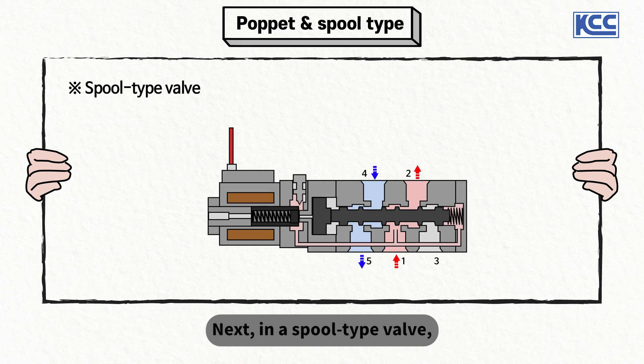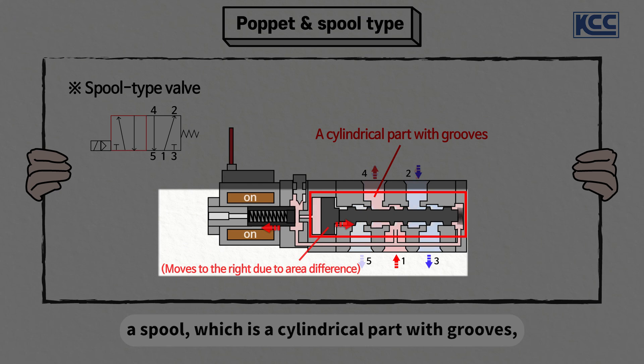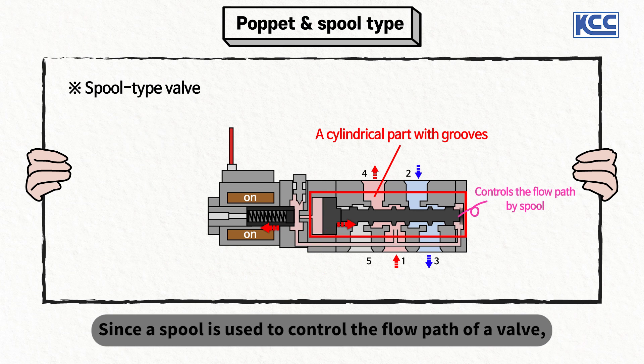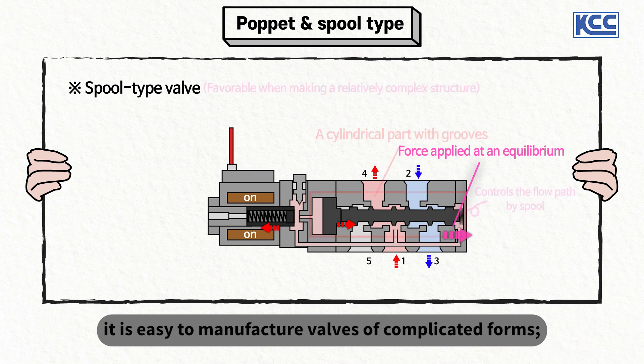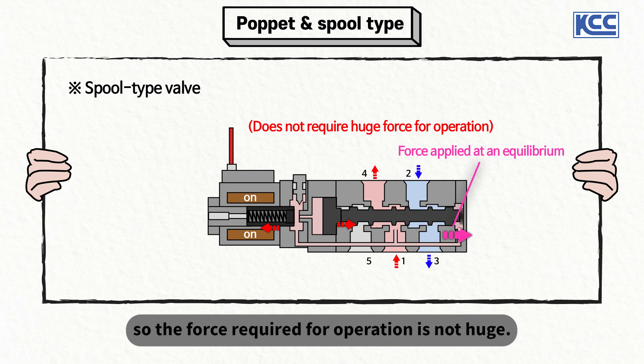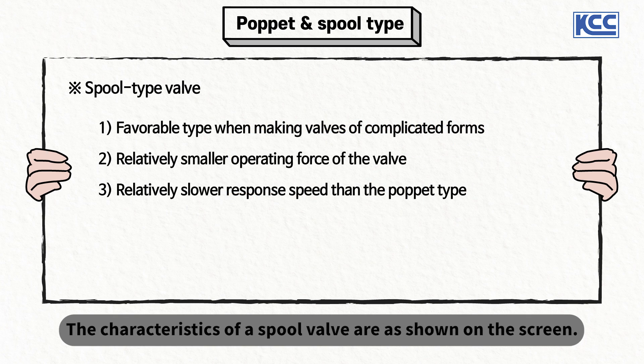The characteristics of a poppet type valve are as shown on the screen. Next, in a spool type valve, a spool — which is a cylinder part with grooves — moves along the axis of a valve to operate it. Since a spool is used to control the flow path of a valve, it is easy to manufacture valves of complicated forms and the force applied to a spool is in a state of equilibrium, so the force required for operation is not huge. The characteristics of a spool valve are as shown on the screen.